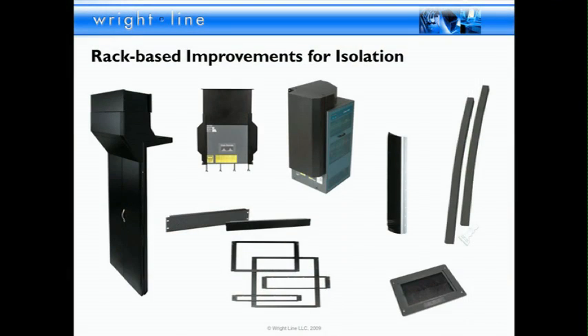As you see here, if anybody's familiar with some of the Cisco networking equipment, that's always a problematic point for Cisco equipment moving in a front-to-back airflow environment when you put in an enclosure. Many baffles exist for those type products to make it front-to-back, including products that normally exhaust out the back, but IT departments like to mount them in the rear because of the connectivity requirements. You need to be able to manage that airflow as well. Many products exist, as well as KoldLok and other brush strips, all good hygiene for the rack.